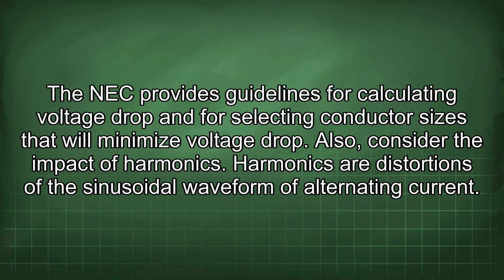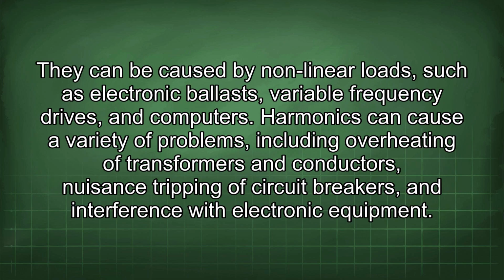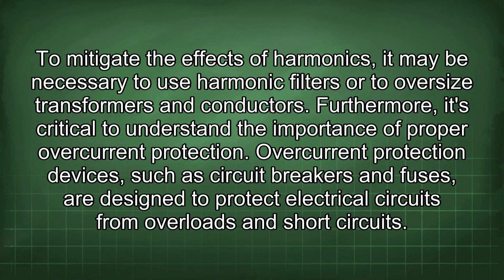Also, consider the impact of harmonics. Harmonics are distortions of the sinusoidal waveform of alternating current. They can be caused by nonlinear loads, such as electronic ballasts, variable frequency drives, and computers. Harmonics can cause a variety of problems, including overheating of transformers and conductors, nuisance tripping of circuit breakers, and interference with electronic equipment. To mitigate the effects of harmonics, it may be necessary to use harmonic filters or to oversize transformers and conductors.